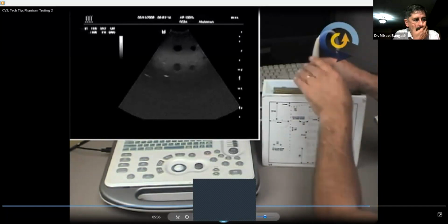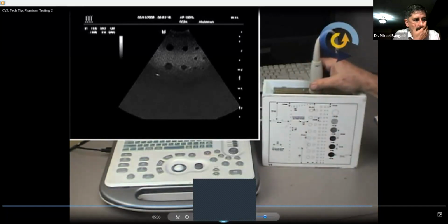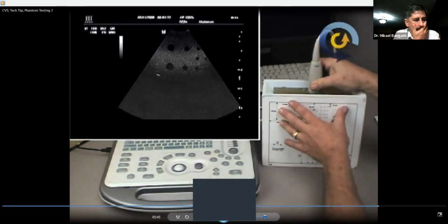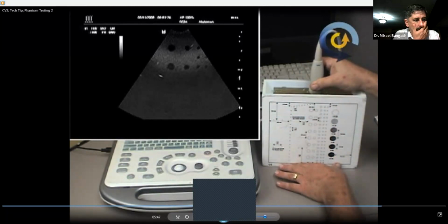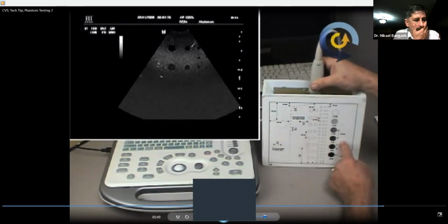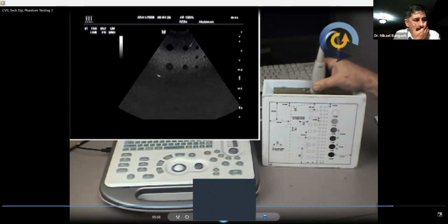And there are very expensive high-end phantoms to do that. One of them is called a string phantom, and it literally is a block of water. It has some material inside that has roughly the acoustic properties of blood, and it has a moving string that has small beads on it. Because of that, it can measure the motion, and it can actually verify that you've got the correct frequency scanning for your Doppler, and it will even do color and show that it's got the right frequency.